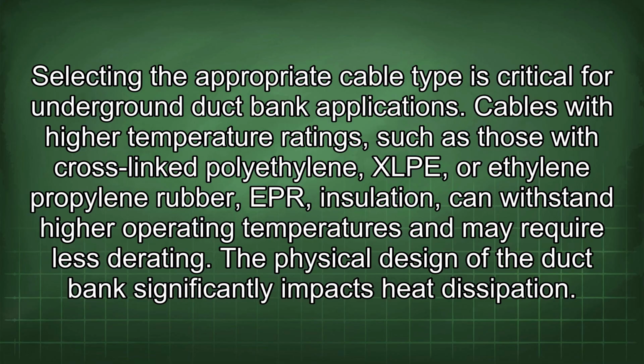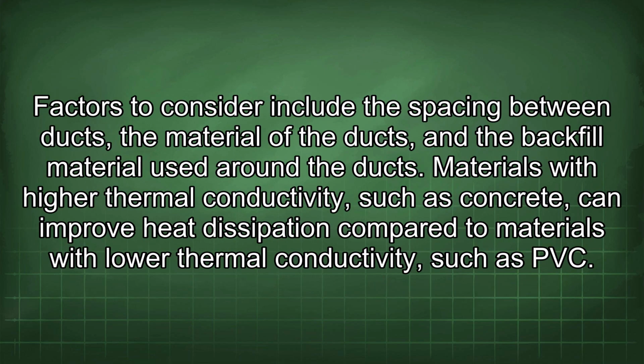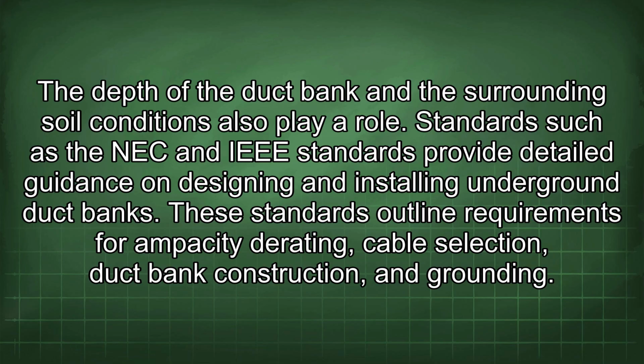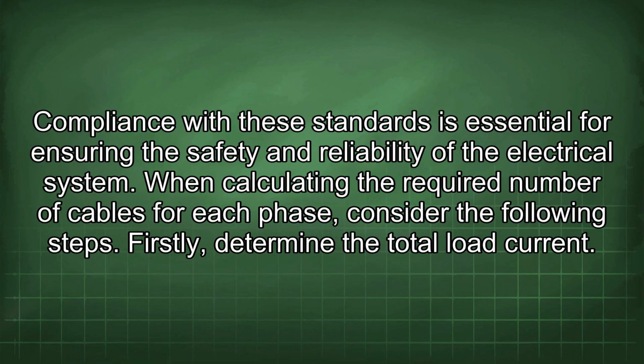The physical design of the duct bank significantly impacts heat dissipation. Factors to consider include the spacing between ducts, the material of the duct, and the backfill material used around the duct. Materials with higher thermal conductivity, such as concrete, can improve heat dissipation compared to materials with lower thermal conductivity, such as PVC. The depth of the duct bank and the surrounding soil conditions also play a role. Standards such as the NEC and IEEE standards provide detailed guidance on designing and installing underground duct banks. These standards outline requirements for ampacity derating, cable selection, duct bank construction, and grounding. Compliance with these standards is essential for ensuring the safety and reliability of the electrical system.